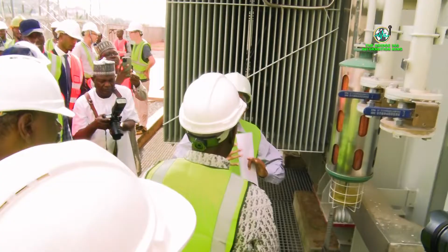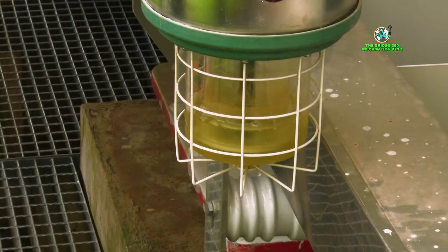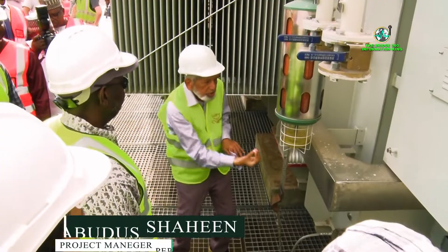This is for breathing of the transformer. As temperature rises, the oil expands, and when it expands, the space inside the transformer is reduced. When the temperature is low, it shrinks down and the level comes down. When the level comes down, it needs to breathe in air, and when the level goes up, it needs to breathe out. So this is the breathing in and breathing out of the transformer.